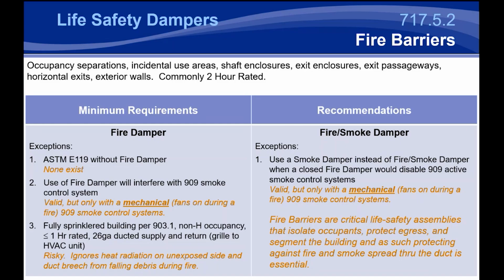Now, your fire damper is certified to protect against that. Fire dampers are required to go through a duct drop test where you install that damper, you actually take a 55-gallon drum with 400 pounds of sand, and you drop it on the duct and make sure the duct can shear away with the improved breakaway connection, and the damper stays in place, protecting that fire-rated barrier.